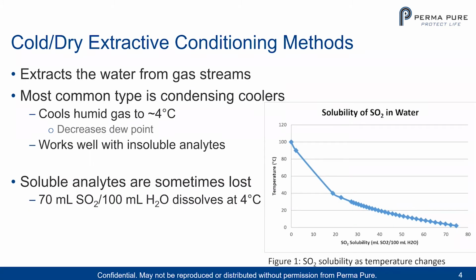So let's start with talking about cold and dry extractive conditioning methods. Really what we're doing is we extract the water from the gas streams or eliminate it. You need to do this because water has two main issues with a sample stream. First of all, and most importantly, if you get liquid water in the analyzers or on the analyzer sensor, the analyzer will not work. You'll ruin your analyzer, which is a big repair. So we need to extract the water from that. And the other thing we need to do is get rid of the water that does interfere with the measurement.